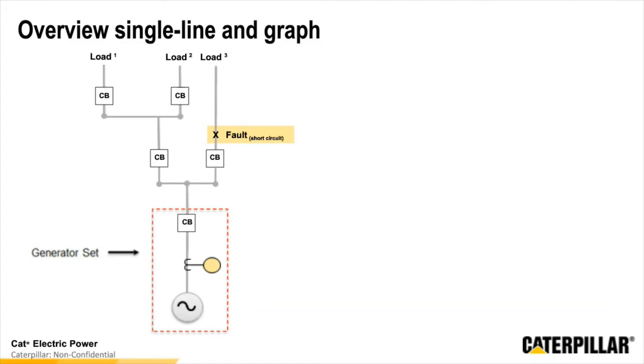So as we start our discussion, again, we're going to look at a single line that we're going to be using throughout the presentation. We've simplified the single line down to remove any references to the utility, an automatic transfer switch, or any of the transformers potentially in the system. What we're really looking at is the coordination of and protections associated with our generator set and the overall systems connection. So the one line starts at the bottom with the generator set.